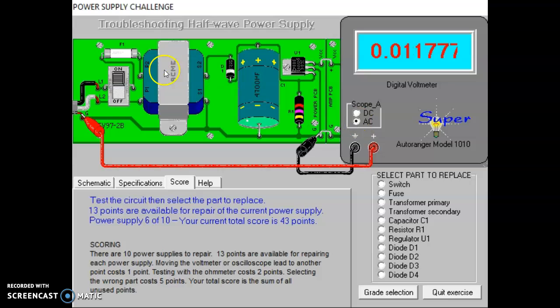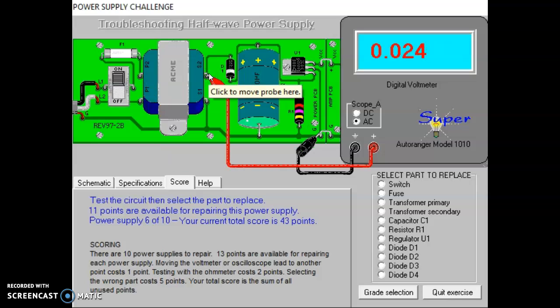AC sense is where we're going to start. Let's look at the transformer. We've got a good primary input. We don't have a good output on the secondary side. Now that doesn't mean the secondary is the problem - the primary could be the problem. So let's first check the secondary.